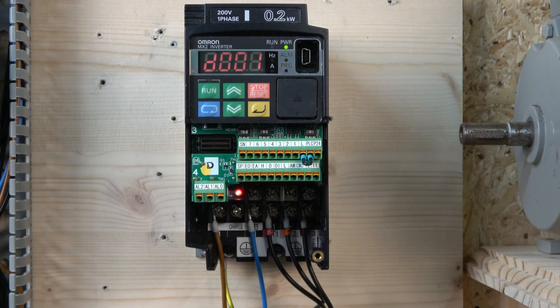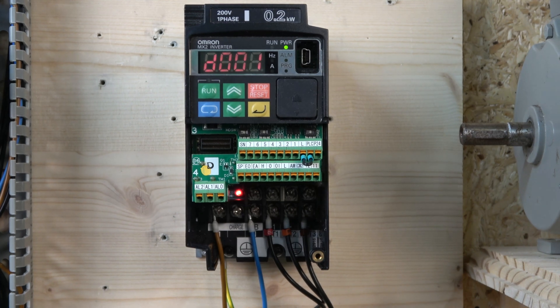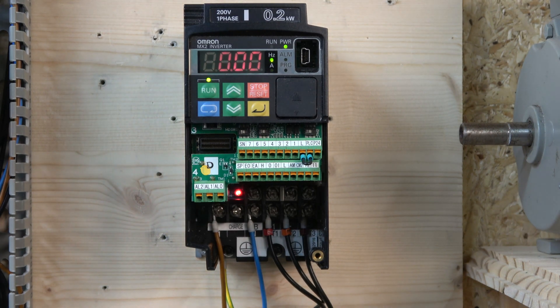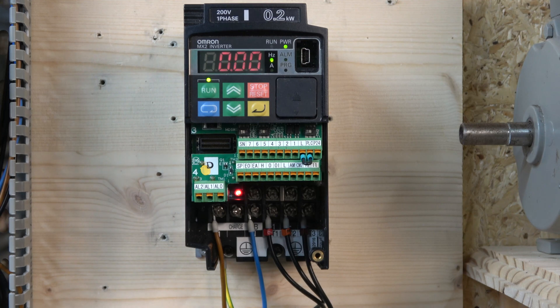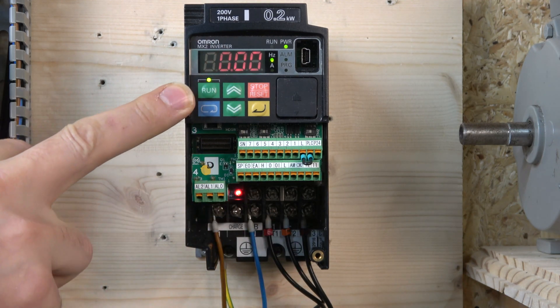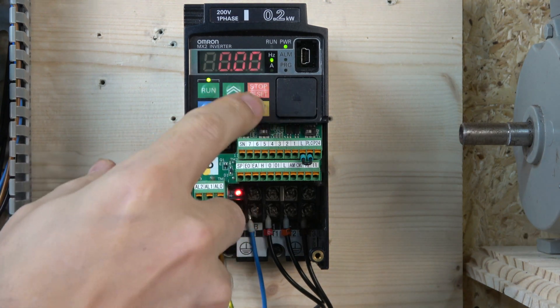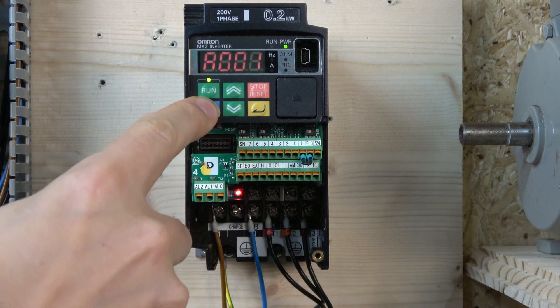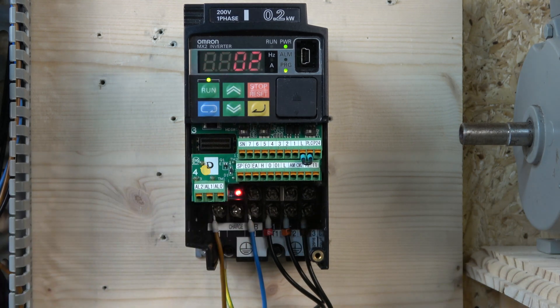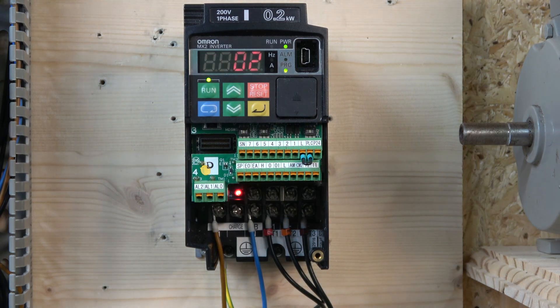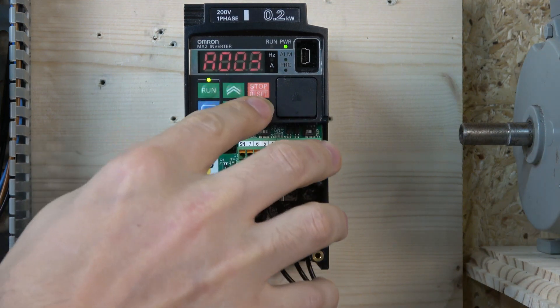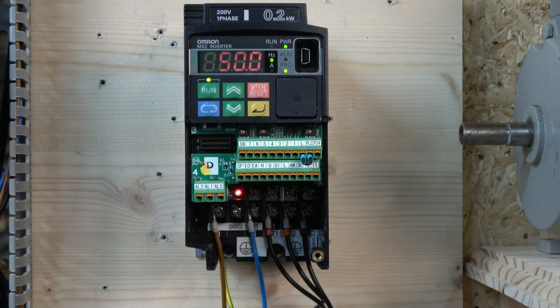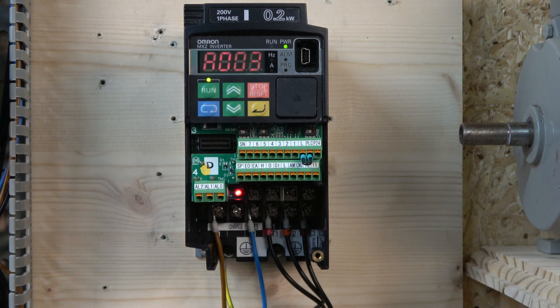Next up, let's enter the motor data. For our motor setup, we're going to be doing an auto-tune. Auto-tune in this drive is quite interesting, so we're going to run you through it step by step. First, we need to make sure we're able to run the drive from local mode. That will be done in A2. We need to make sure that's on 2. Then we're going to check A3 as well. In A3, we need to make sure our base frequency matches whichever country you're in. Ours is 50 Hz.